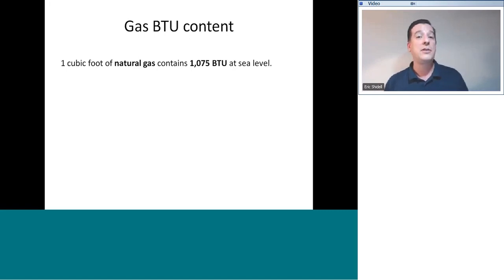Ask them, too, if it's different between the winter and the summer. Some places are. Some places have winter gas and summer gas, just like gasoline. So find out about that. Cool. Good stuff to know for your local marketplace. But for the course of this program, we will consider that natural gas has 1,000 BTU per cubic foot, because that's the average, and that's what your utility providers are striving for. It's also what your gas appliance manufacturers factor in when they design machinery.